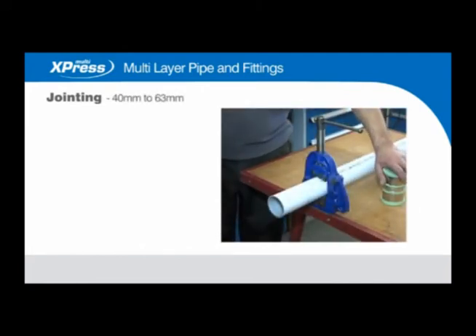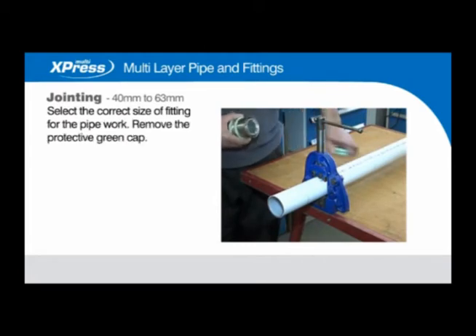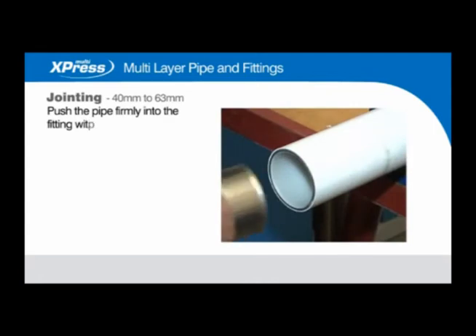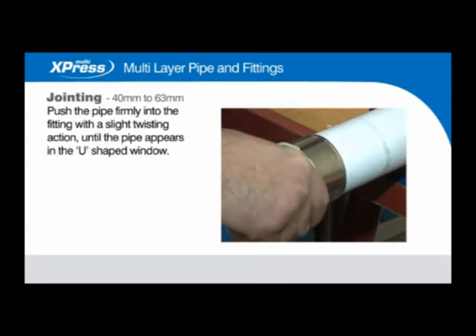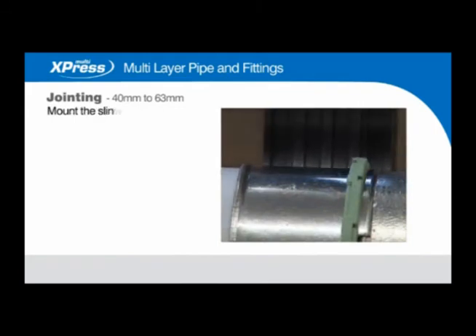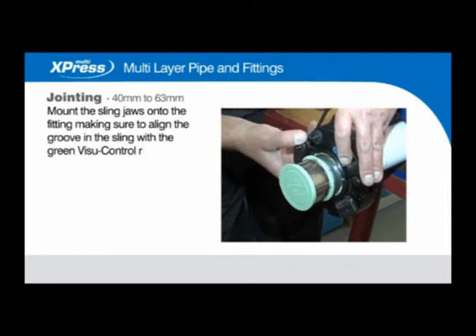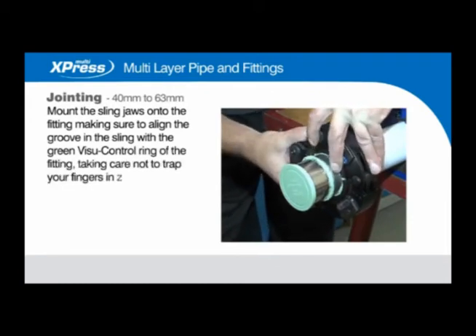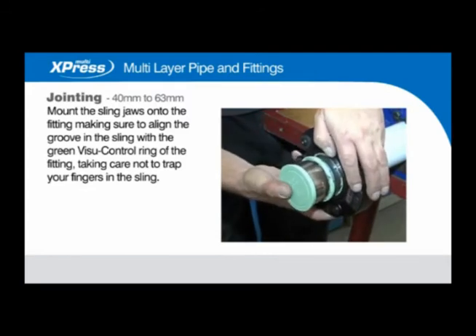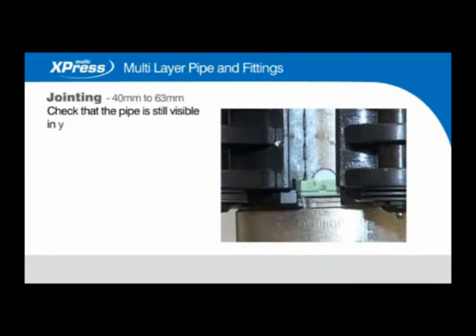Jointing 40mm to 63mm. Select the correct size of fitting for the pipework and remove the protective green cap. Push the pipe firmly into the fitting with a slight twisting action until the pipe appears in the U-shape window. Select the correct sling jaws for the joint being made, checking they are free from damage. Mount the sling jaws onto the fitting, making sure to align the groove in the sling with the green Visu-Control ring of the fitting, taking care not to trap your fingers in the sling. Check that the pipe is still visible in the U-shape window.